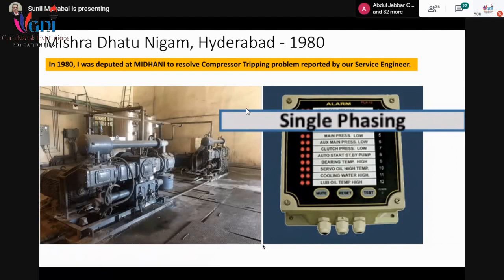It is a common thing that happens when a single fuse blows, and it can be because of various reasons. If the moving contacts of the contactor are not good, then also it can happen. So the single phasing was tripping it, and there was no obvious reason when I checked with a multimeter. Then I underwent a training with Larsen and Toubro on the switches.